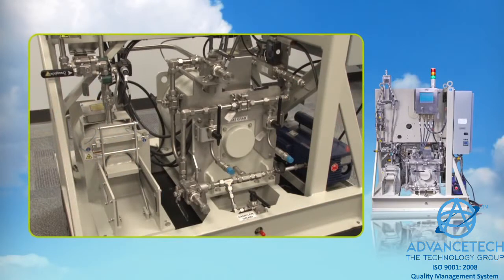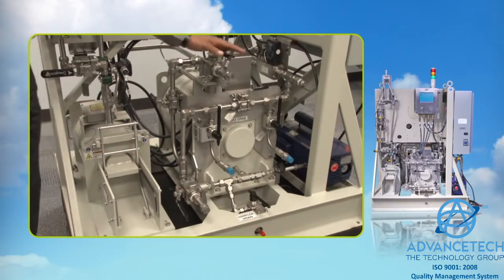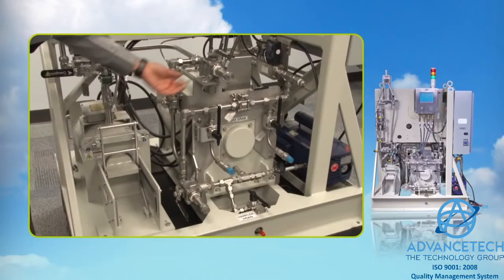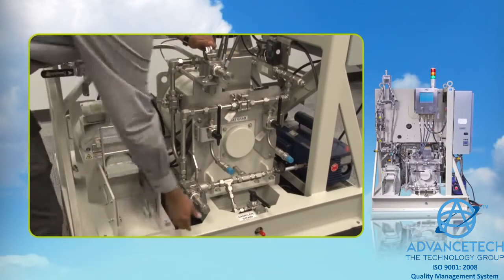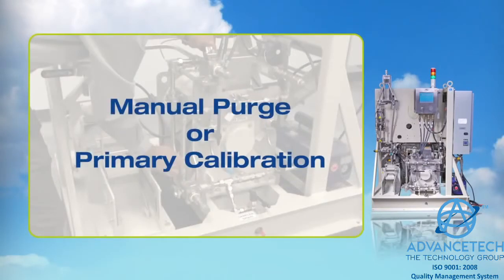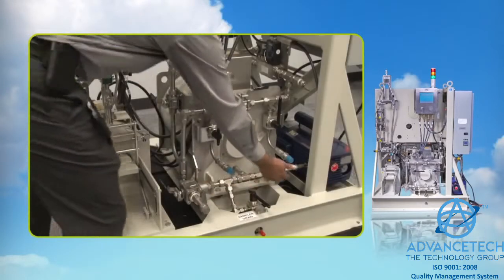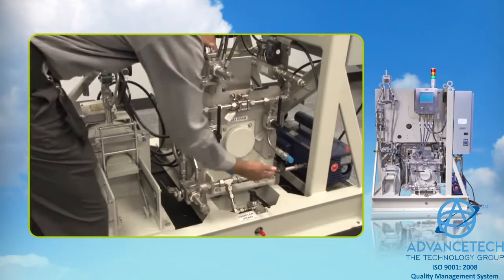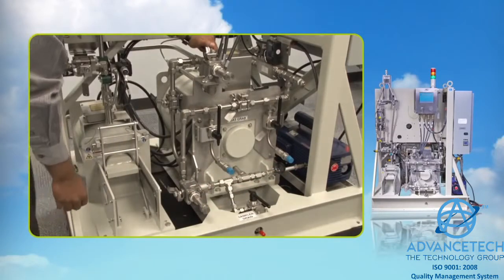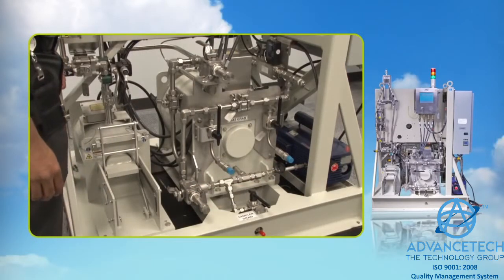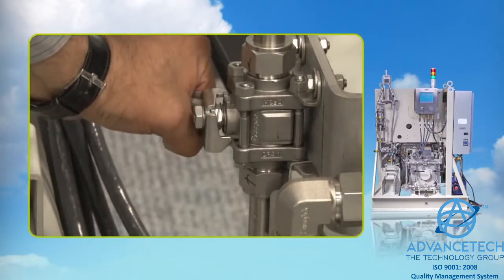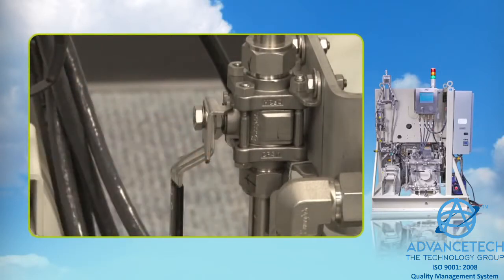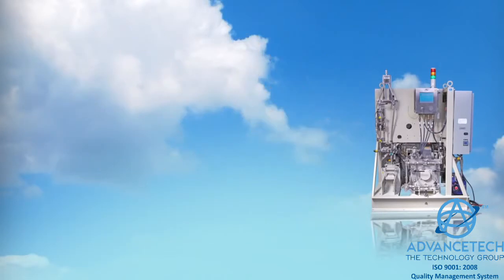Two three-way valves are provided before and after the noble gas chamber. These can be used for manual purge or primary calibration. The system also includes a vacuum pressure transducer that constantly measures the pressure inside the chamber and dynamically compensates the concentration value. A bypass valve is also available to bypass the noble gas chamber when maintenance is being conducted.